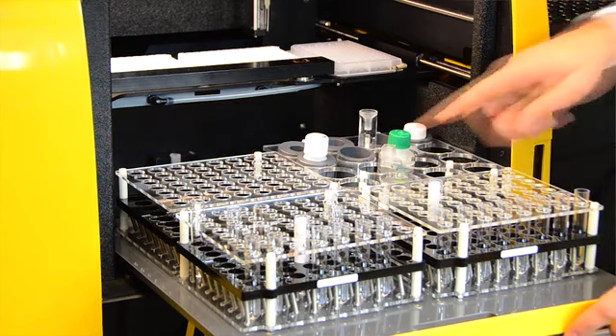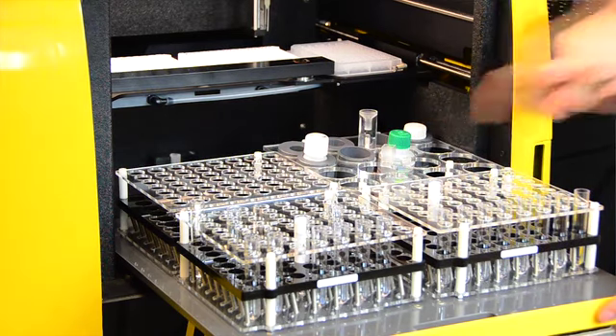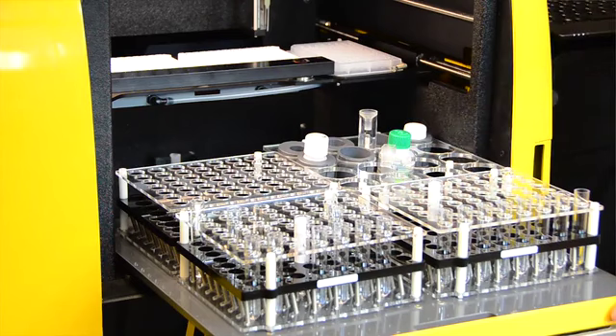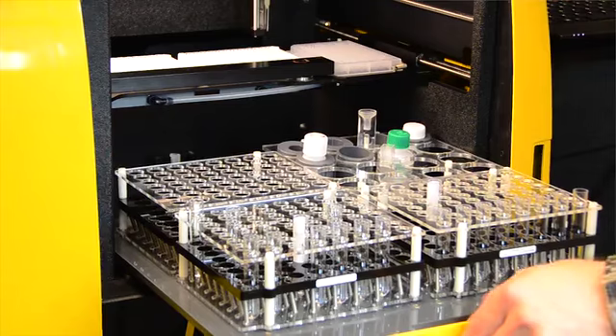All right. You will also see on this reagent rack is a wash cup, as well as a calibration cuvette. The calibration cuvette is just used for service PM reasons, and the user does not use it in any way. And the wash cup, however, is a very important feature that allows us to clean off our probe. Now, with that said, I'm going to move up to the probe.